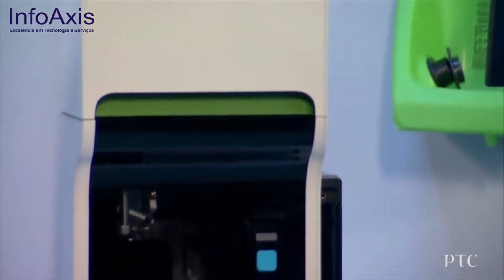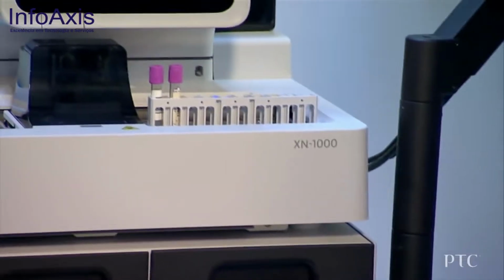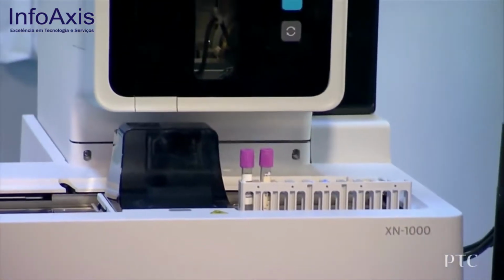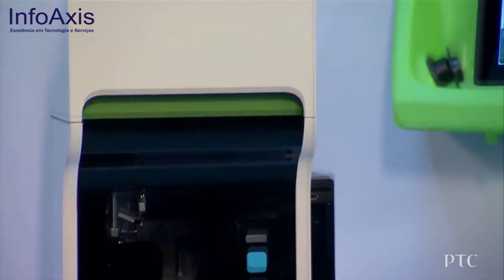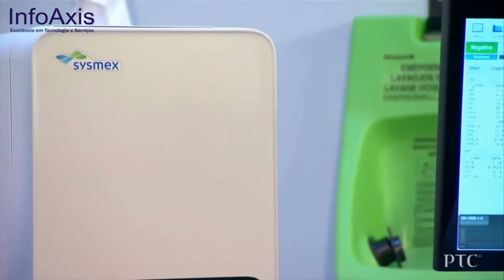Our service engineers already benefit from a connected environment that leverages Thingworx, machine learning, and integrates data from various sources to help them deliver better and more proactive service. Because the Sysmex blood analyzers, like the one you see here, are smart, connected products, service engineers can already identify issues on the devices, remotely calibrate, and predict several potential short-term causes of failure without even touching the analyzer.